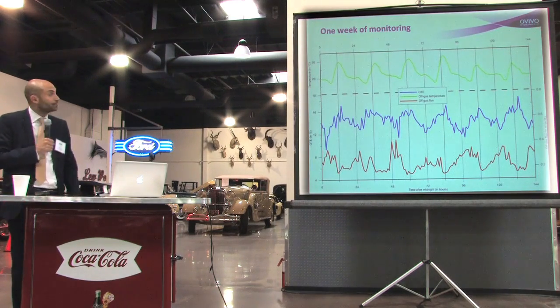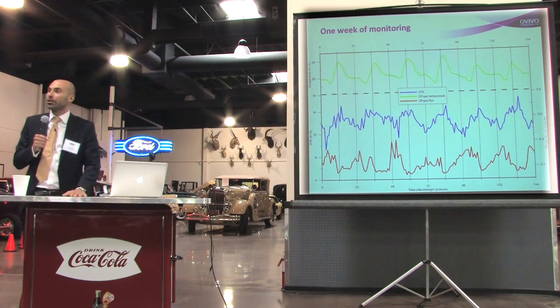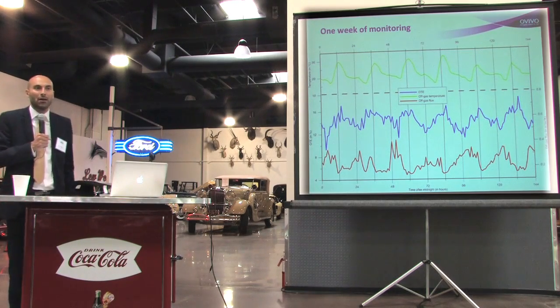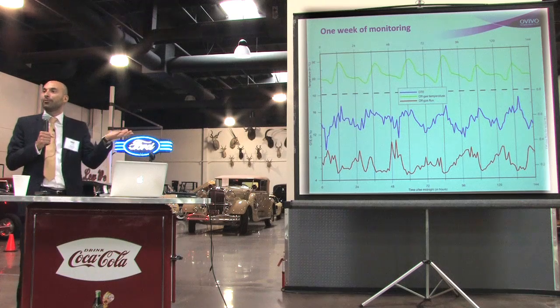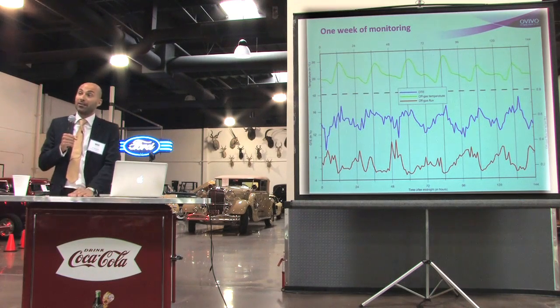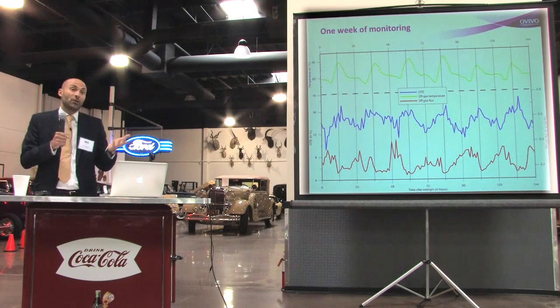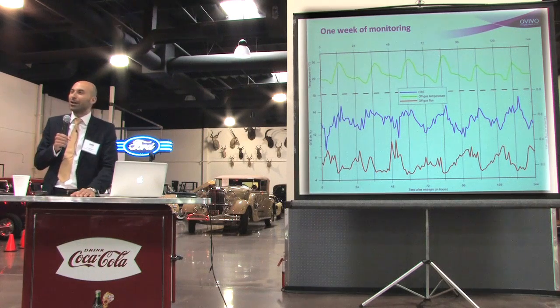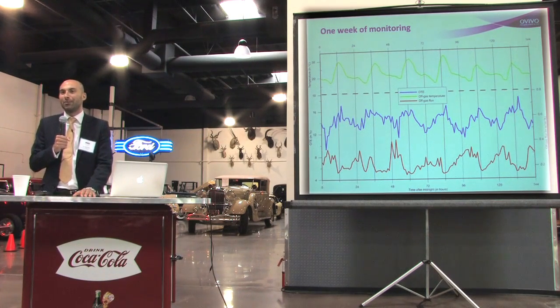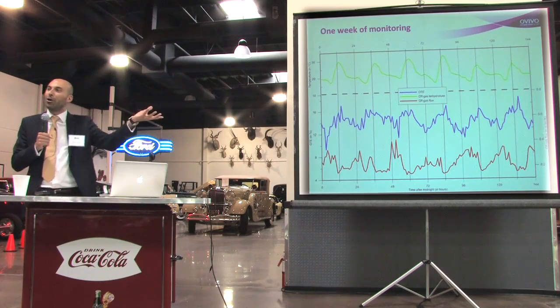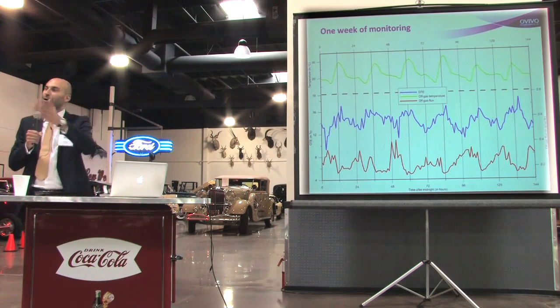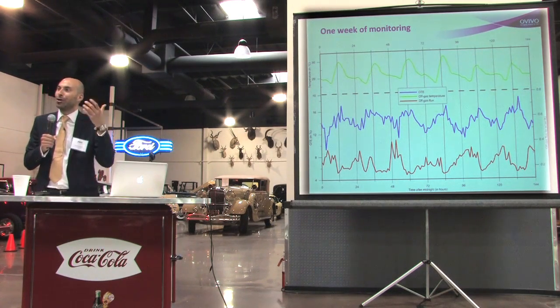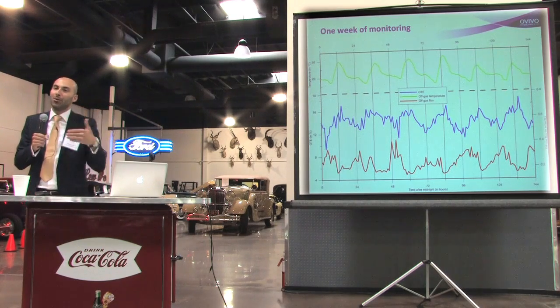This is a week of monitoring at one of the local plants; my students go out about every two weeks to replace the dryer consumable in the analyzer, but it runs on its own. You can build your own for about $4,000–$5,000 in parts. A plant the magnitude of Orange County spends hundreds of thousands of dollars on power per week, so $5,000 is like the cost of a DO probe — plants could add efficiency analyzers alongside them and see aeration efficiency right in the control room.